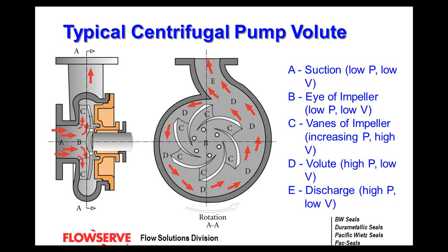At point A, the suction, you start with low pressure and low velocity. As it enters through the impeller eye and into the impeller vanes, these increase the pressure and velocity. As it passes through the volute, pressure remains high but velocity starts to slow. At the discharge you have higher pressure and lower velocity. GPM in equals GPM out; what the pump does is impart head and increase the energy of the fluid.